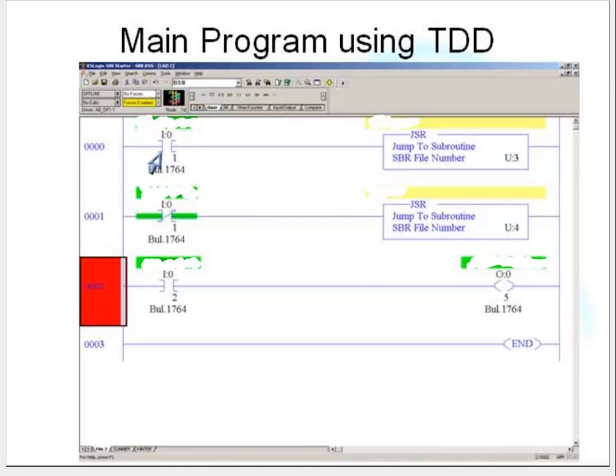Okay, so I now go off and I get my hardware, my wiring diagram out, and I look up input 1. And I find that input 1 is actually the summer switch.